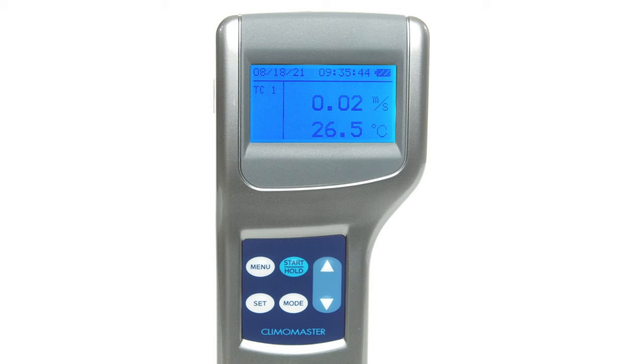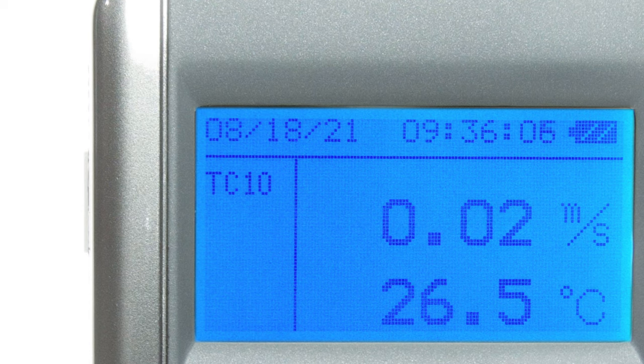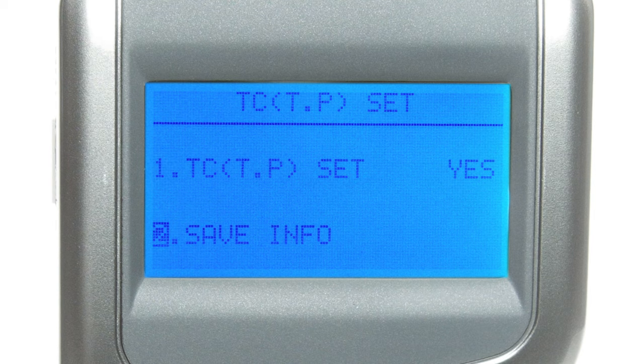When you first turn on the instrument you'll find yourself in normal mode. In this mode you cannot save any data and the display is updated every one second. The navigation buttons allow you to select the time constant — 1, 5, or 10 seconds — for measuring in normal mode. This is useful for measuring turbulent airflow since it averages readings over a set time period. By default, the time constant is only effective for air velocity and airflow in normal mode. If you want to make it effective for air temperature, humidity, and pressure, you'll have to navigate to the main menu and the utility section, where you'll select TC (T.P) Set and make sure it's turned on and saved before exiting.